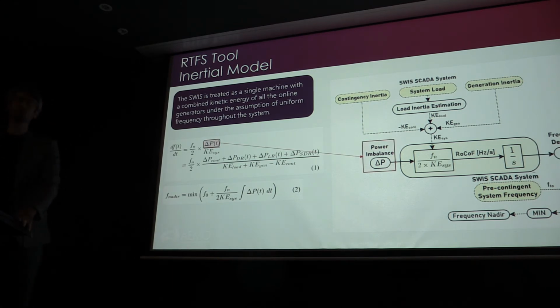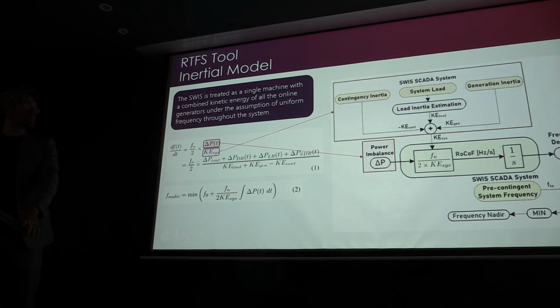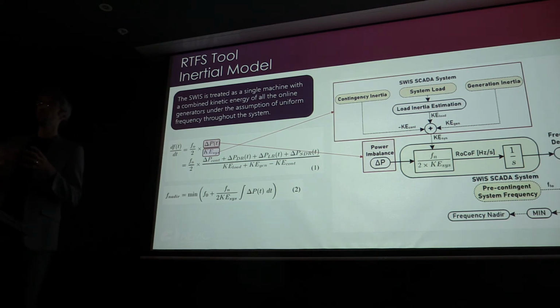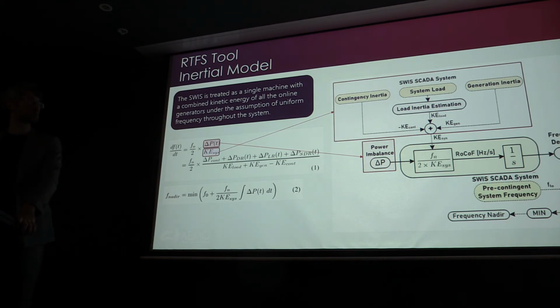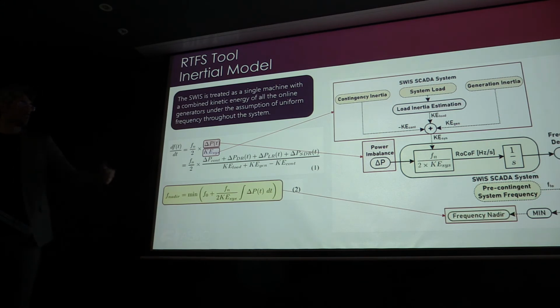So we've got delta P, which is the imbalance in power, and system inertia. We've got generation inertia, or the sum of all the inertia of the generators together, from the SCADA system, and we know the system load. Based on the equation we've got for load inertia calculation, we estimate that, and we know which unit is the largest and the contingency size of that unit. So all together we feed it into the swing equation, and then we can calculate the frequency nadir, or minimum point of the frequency trace the tool predicts.